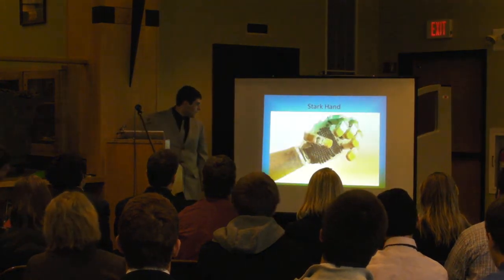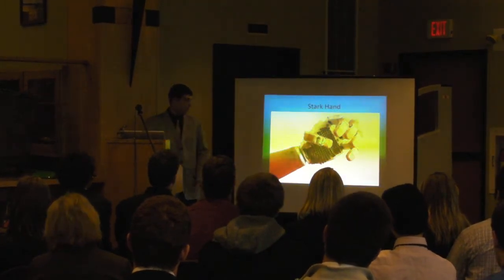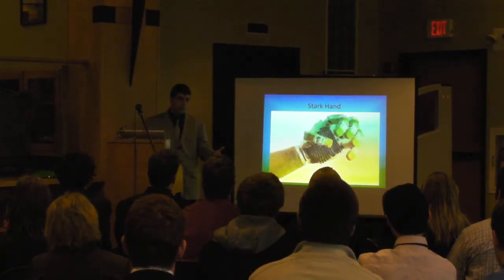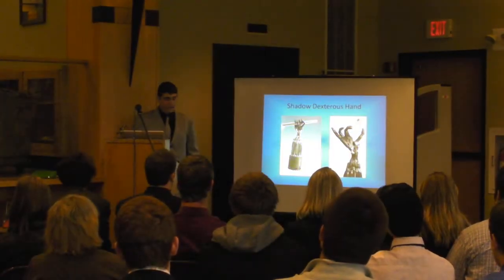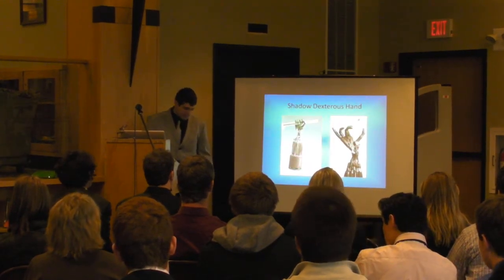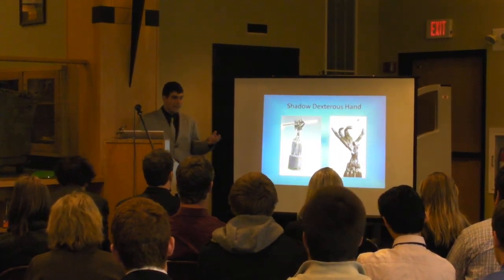This is the Stark hand, which is purely mechanical — there's no electronics involved. This piece down here fits over the stump. It's got a cable that goes along the back of it, attaches to the shoulder. They shrug their shoulder — this one is voluntary opening, so it will open when you shrug your shoulder and pull on a cable. It has springs to pull it closed around whatever object you're trying to pick up. This is the Shadow Dexterous hand, which is not a prosthetic, but it's the current leading technology for any type of moving appendage.